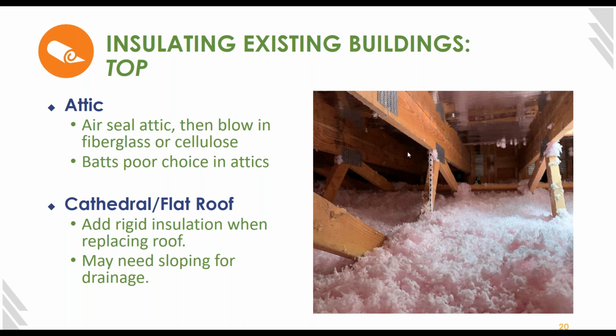If you go up there, there's going to be bits and pieces of stuff that fall off the roof — that's pretty common. But if you see any area that's really dirty for no reason, the reason is that air is either coming out or going into the building through that location. You probably have air leakage.